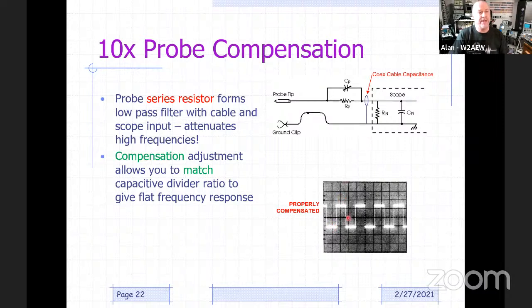But because I've got fast edges on it, there's higher frequency content, right? As you know from square waves, you got energy at all of the odd harmonics. So those odd harmonics are higher and higher in frequency, and they'll get affected more by the capacitive voltage divider. So what you do is you hook your scope probe up to that compensation signal, and you adjust that capacitor on the probe to get a perfect looking square wave.